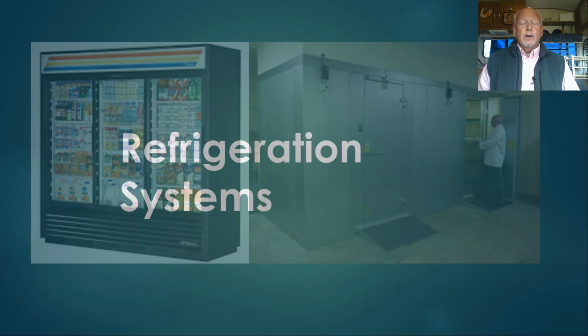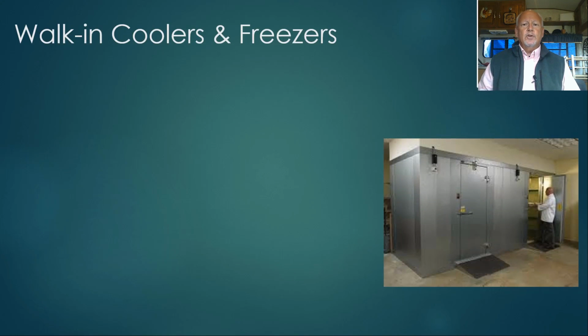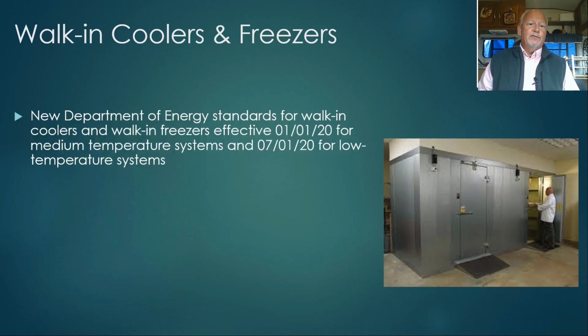So we're going to move on from service water heating to refrigeration systems. There've been some changes in the requirements for walk-in coolers and freezers. There are new Department of Energy standards for walk-in coolers and walk-in freezers that went into effect on 1/1/2020 for medium temperature systems and on July 1st, 2020 for low temperature systems. And those new energy standards have been incorporated into the 2018 WSEC.